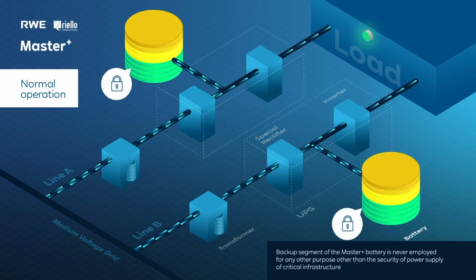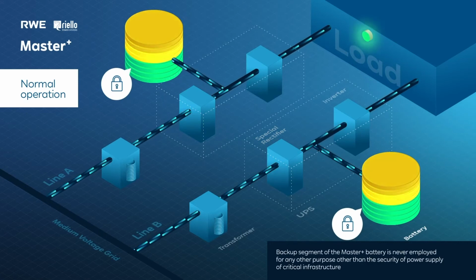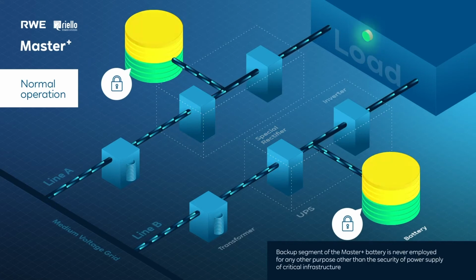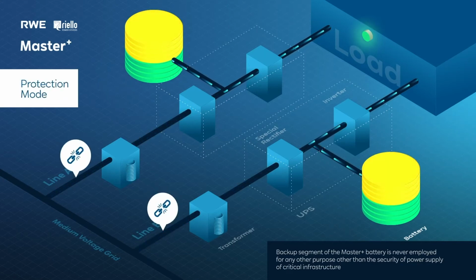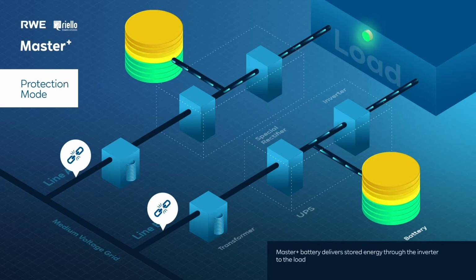The backup segment of the Master Plus batteries is always ready to be used in case of any power supply problem. It is never employed for any purpose other than the security of power supply of your critical infrastructure. In case the power supply is in danger or not within the permitted range, Master Plus switches to protection mode, instantaneously supplying the energy stored in the batteries through the inverter into the load.